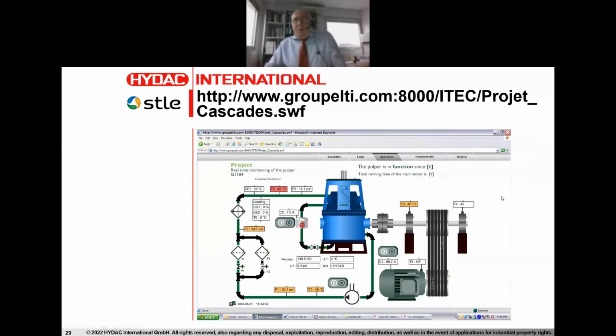This was a pulper in Quebec this time. And one of the things that we were able to record and observe immediately here is that the heat exchanger has failed. This was very valuable and real information this time. Because if you look at the normal temperature of 46 degrees C at this bearing and 49 degrees C here downstream of the pump, downstream of a heat exchanger, you should not be reading 45.